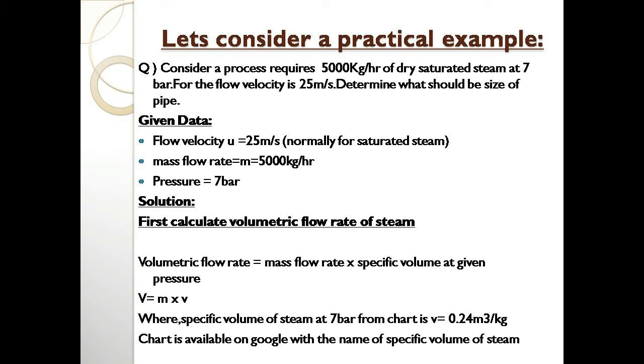The given data: flow velocity = 25 m/s, mass flow rate = 5000 kg/hr, steam pressure = 7 bar. Moving to the solution, we first need to calculate the volumetric flow rate of steam, since we have mass flow rate, not volumetric flow rate. Volumetric flow rate equals mass flow rate multiplied by specific volume at the given pressure.